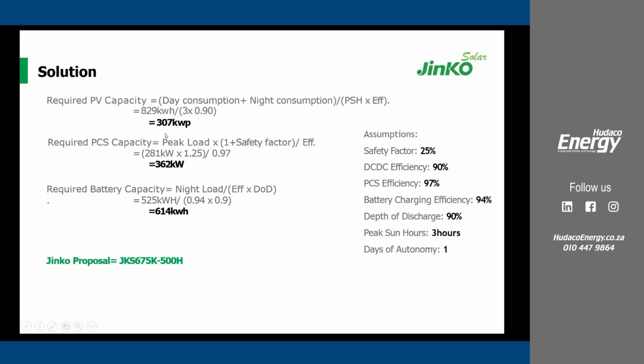On the PV capacity, we also need to factor in another scenario. Let's say the required PCS was around 162. Ideally in this case we could choose maybe 250 kilowatts for the PCS. But for the DC-DC, we also need to make sure the DC-DC unit can accommodate up to 307 kilowatt peak.